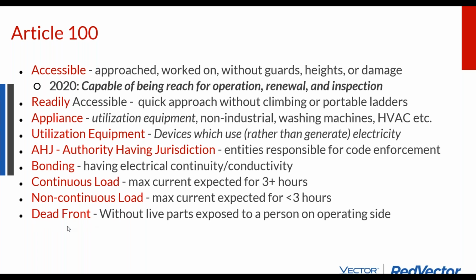Here's a term, dead front. It's without live parts being exposed to a person on the operating side. What that means is, when you open up the lid to your electric service panel and you look into it, you don't see the wires, you just see the breakers and this piece of metal that covers it. That's a dead front. Sometimes when you open up a solar breaker box, you just look straight into the terminals and see the wiring. I often will get a customer say, well, if I stick my hand in there and touch those things, will I kill myself? And the answer is, yes, you will. So that readily accessible exterior disconnect switch needs to have a dead front on it, so that if someone curious opens it up, there's a guard for them.